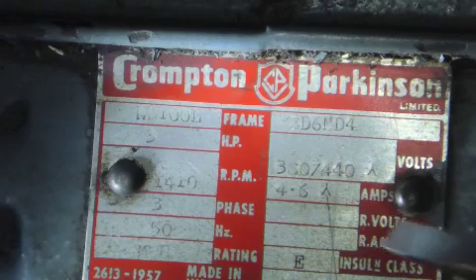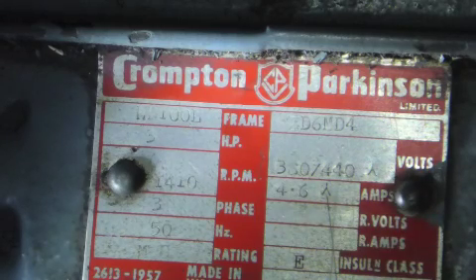However this motor as you can see has only one figure for the amperage rating which means it's not a dual voltage motor and probably won't be happy if you try and run it using a converter that produces 240 volts three phase.